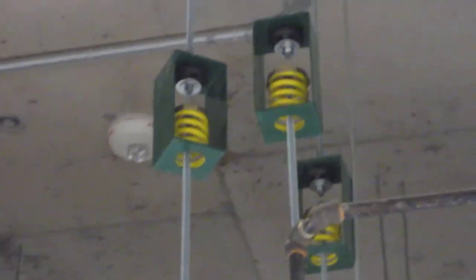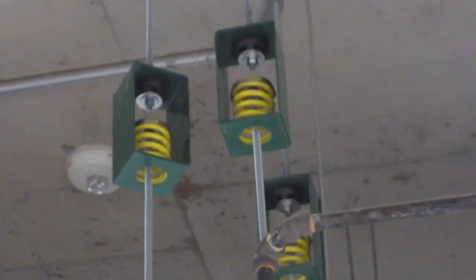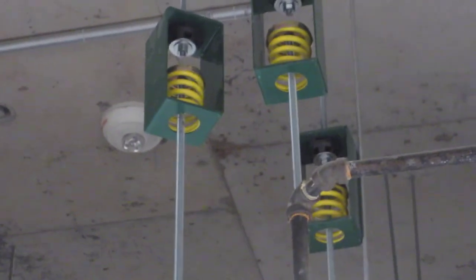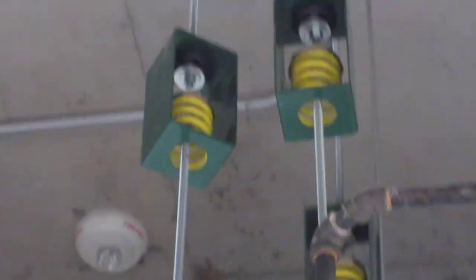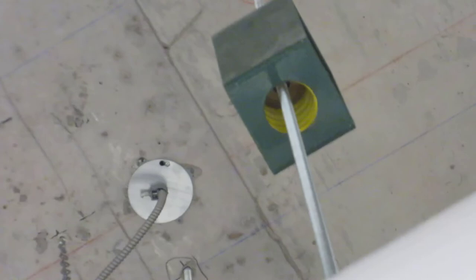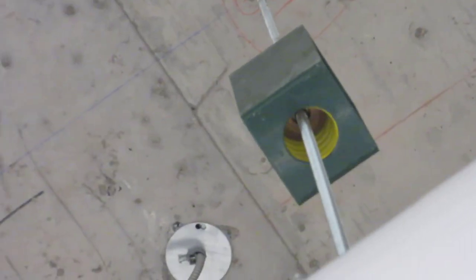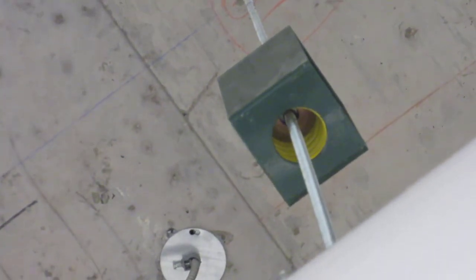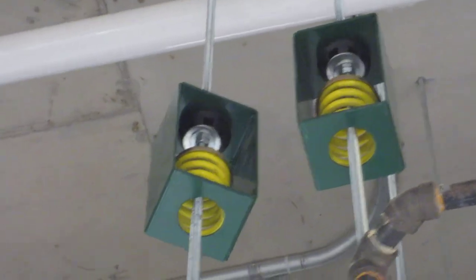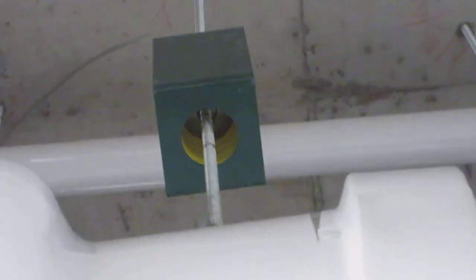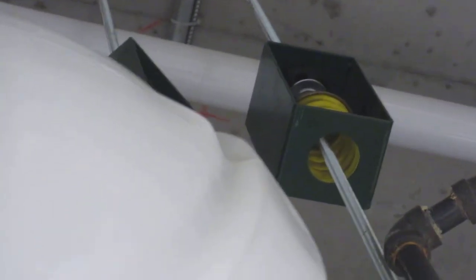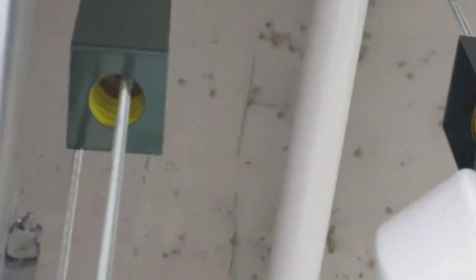It is better than rigidly supporting the pipe directly to structure, however it may not prevent noise problems depending on how much vibration there is and how the building is built. Vibrations can travel very far in steel pipes, and just isolating the first few feet is often not adequate. Some specifications require spring hangers for the first 50 or even 100 feet away from vibrating equipment. If there were a problem here, it would not be too difficult to cut in additional isolators to help reduce structure borne noise through the pipes.